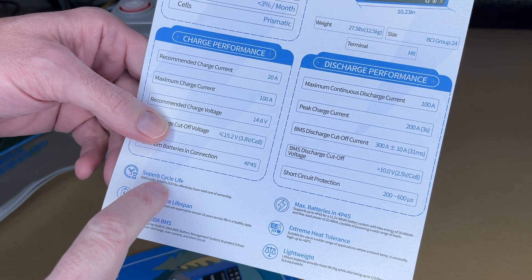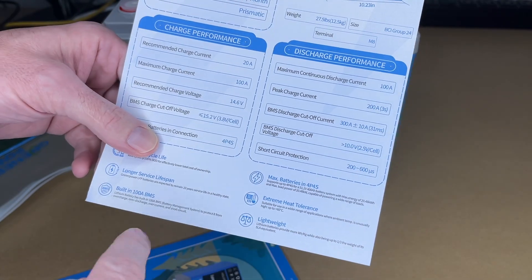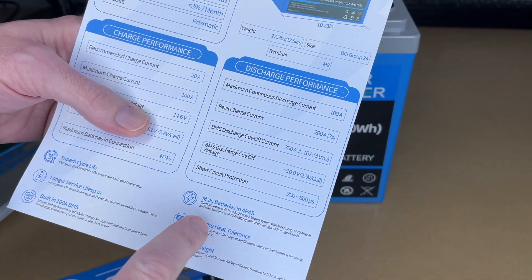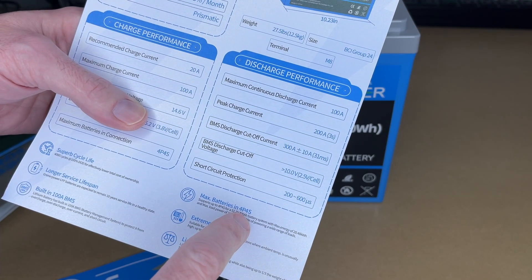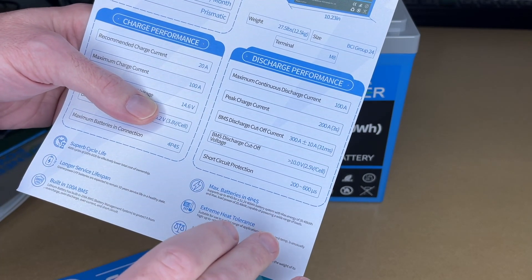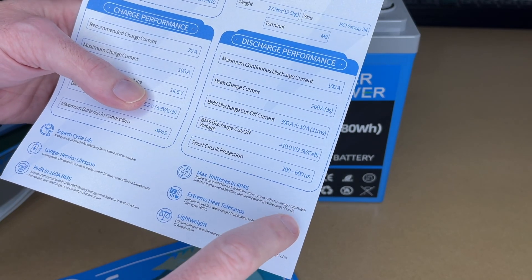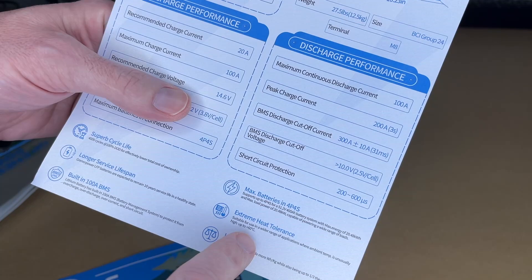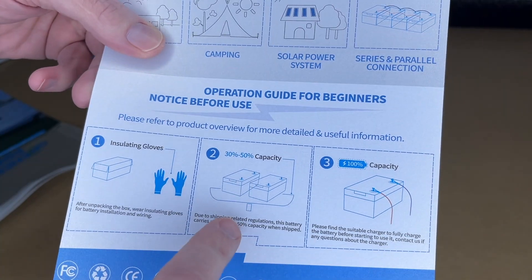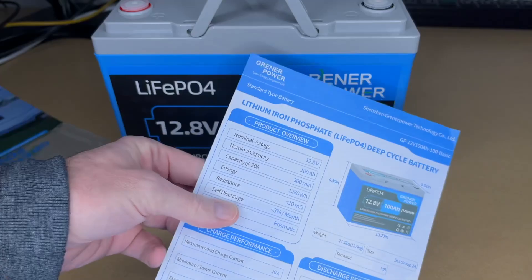There are 4,000 cycles at 100% depth of discharge — if you don't do 100% depth of discharge you should get even more cycles. It has a built-in 100 amp BMS with overcharge, over-discharge, over-current, and short circuit protection. You can hook multiple together: up to 4 in parallel and 4 in series, giving you 16 batteries total for 20,480 watt hours. It has heat tolerance up to 60°C (140°F). It's stored at 30–50% capacity, and they recommend charging to 100% before use.